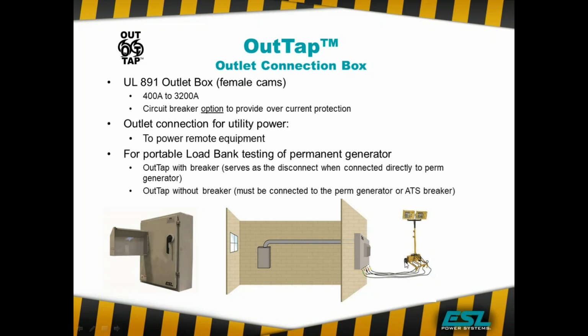Sometimes they use them when they're going to do a renovation or expansion and they don't want to bring in a lot of portable generators. We've installed a number of these on some distribution facilities and other types of facilities where they're going to start a major renovation, and they just want to be able to quick connect in certain equipment. And then finally, this can be used for connection of a portable load bank for testing your permanent generator.